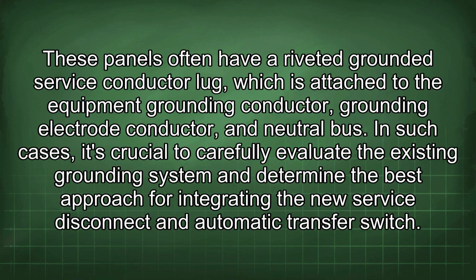These panels often have a riveted grounded service conductor lug, which is attached to the equipment grounding conductor, grounding electrode conductor, and neutral bus. In such cases, it's crucial to carefully evaluate the existing grounding system and determine the best approach for integrating the new service disconnect and automatic transfer switch.